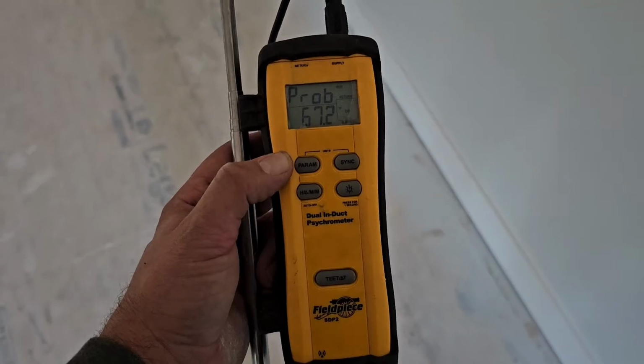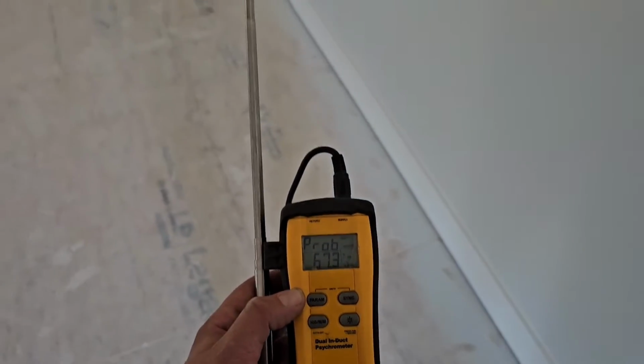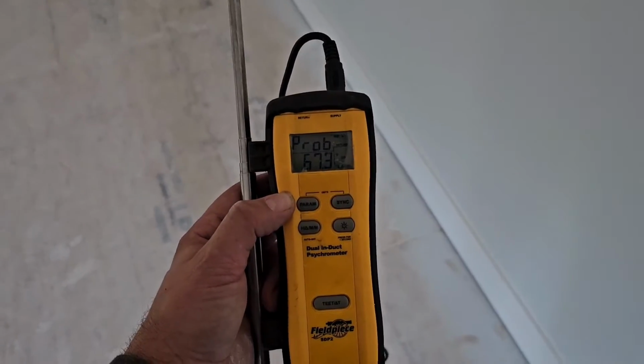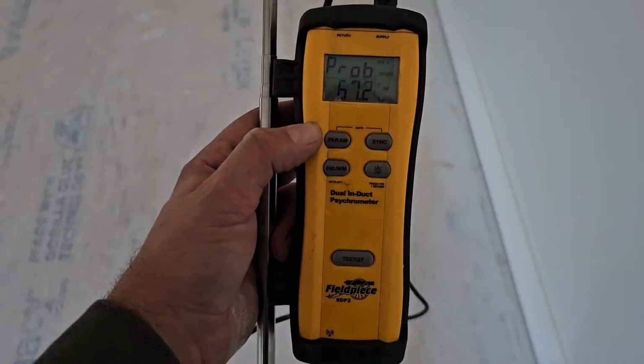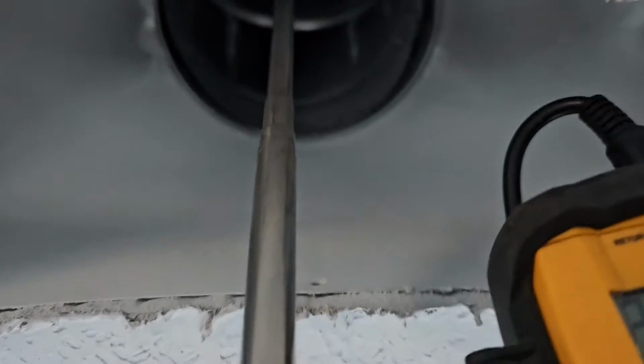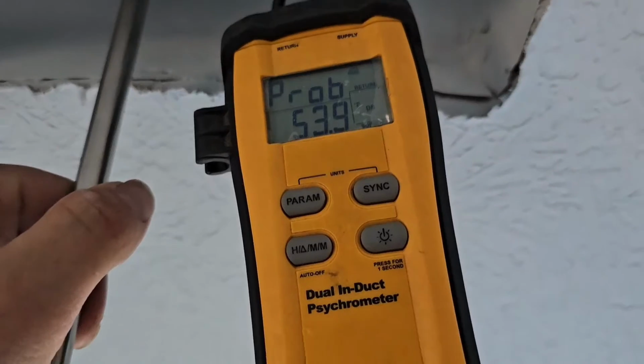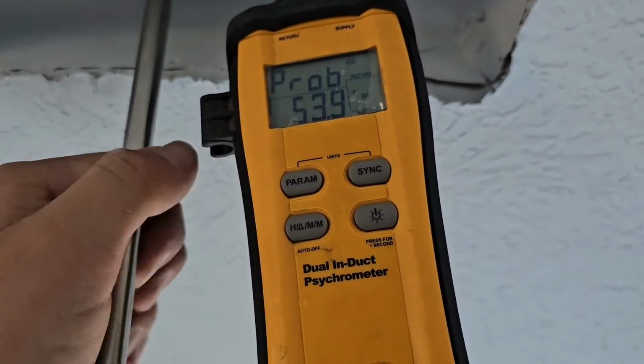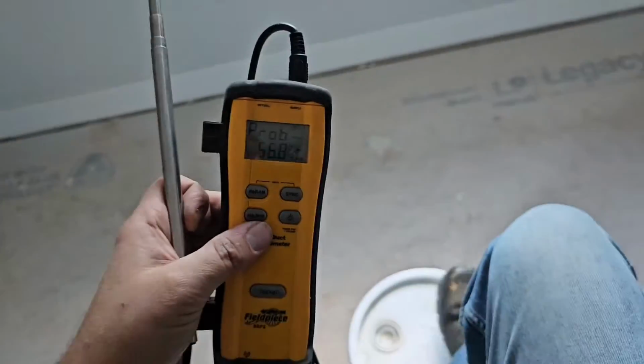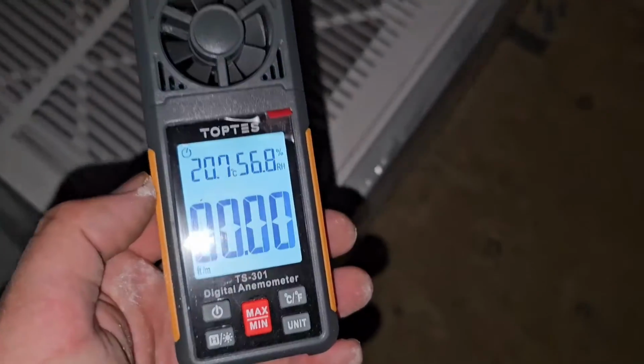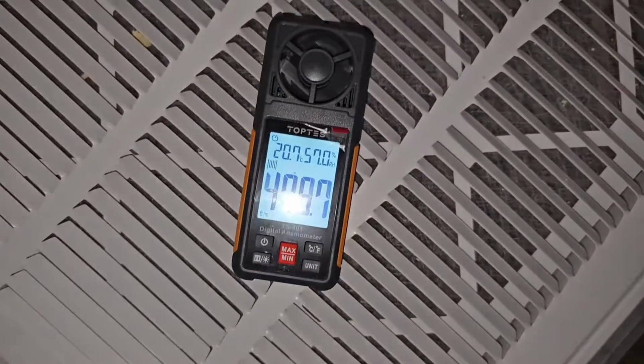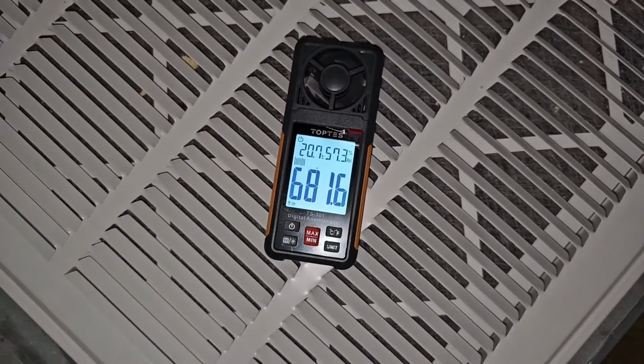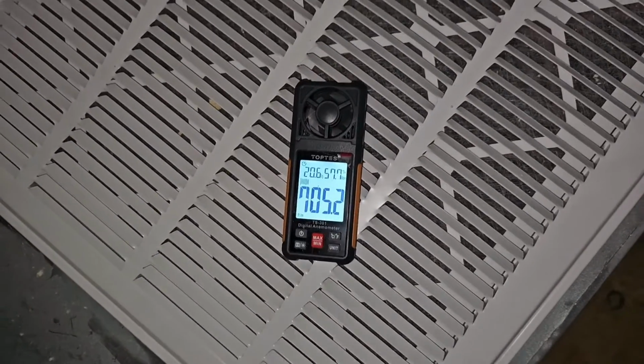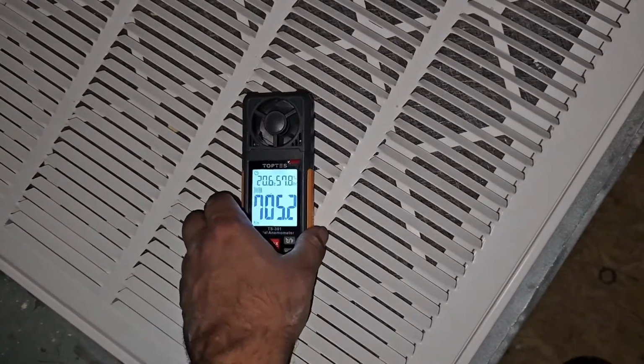All right. Temperature in the house is 67 degrees. Let's check the temperature of the supply air. 53-degree supply air temperature. Definitely need to reduce the fan speed, because that's only like a 14-degree split. We need at least 18. Upstairs return grill. Woo! That is a lot.